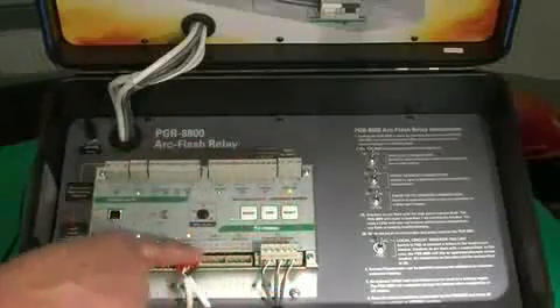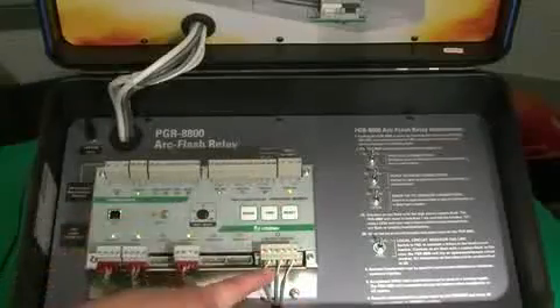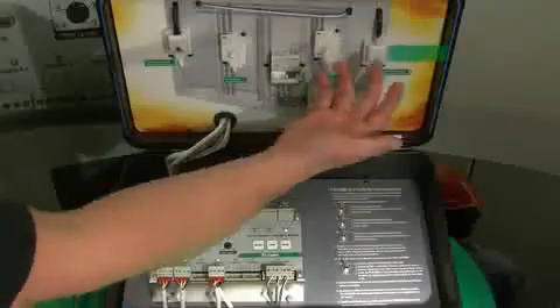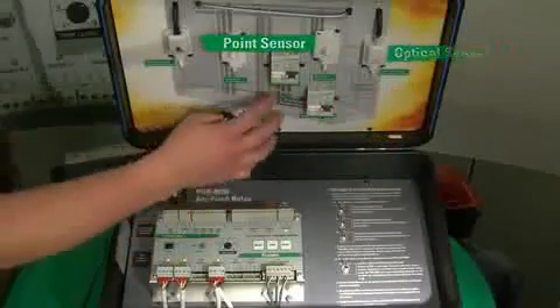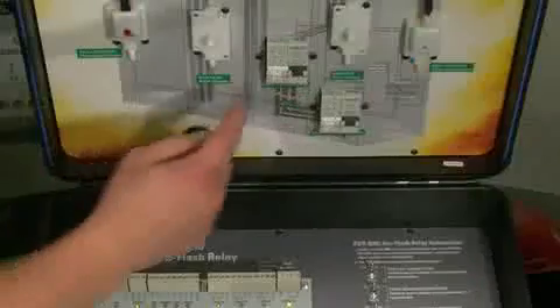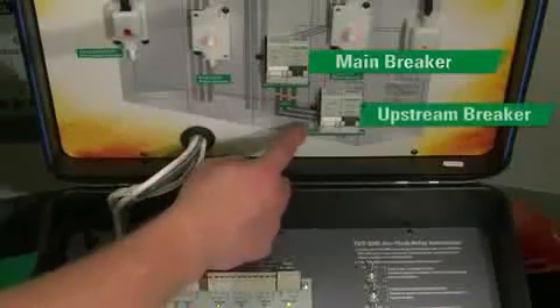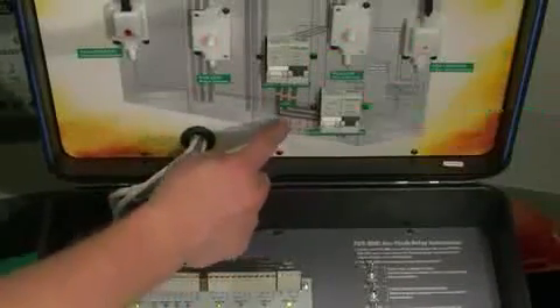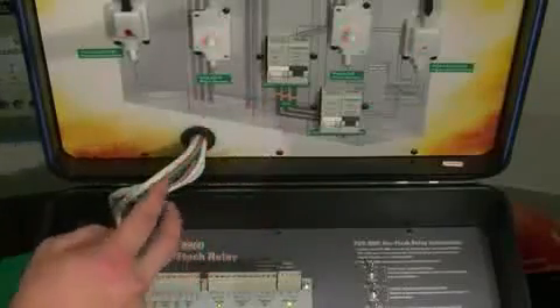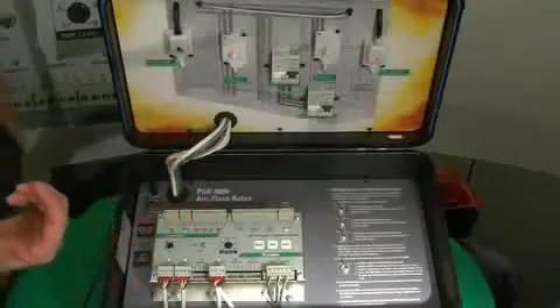What you're seeing here is the relay itself. These are connections for the sensors. These are our CTs. These sensors are connected to each one of these, both optical and point sensors. These are our two breakers that are representative of our main breaker, and then a secondary breaker that's actually upstream of the main. We can trip both of these systems with some of the optional settings in the relay.